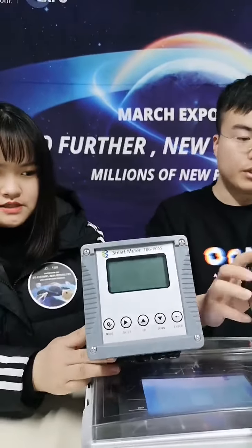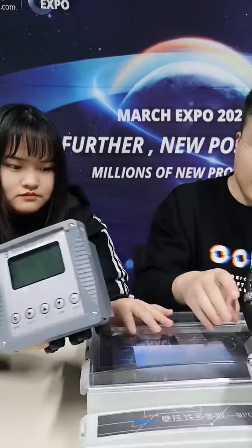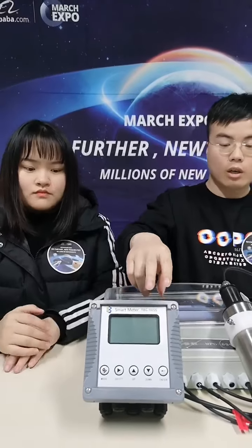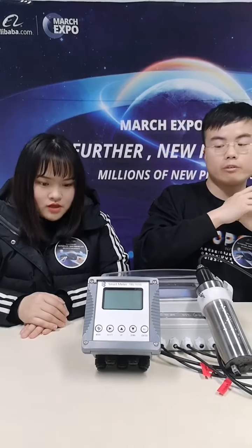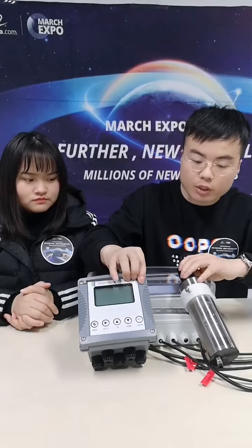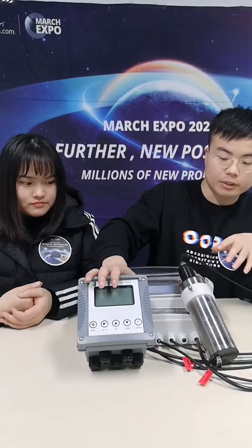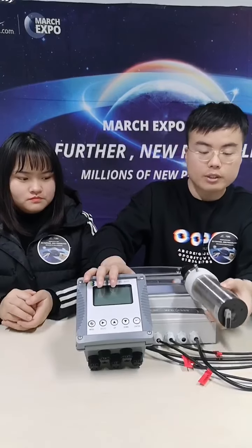This sensor can connect not only to our multi-parameter controller, but also to our controller. This controller has a digital protocol, Modbus RS485, and also three relays and 4 to 20 mA outputs to control your pump, control your wiper, and upload the data to your system. When this sensor is connected to the controller, we can get very accurate data from it, and the sensor needs only light maintenance, because we can set the wiper interval. Every 5 minutes it will clean itself, so it is very easy.